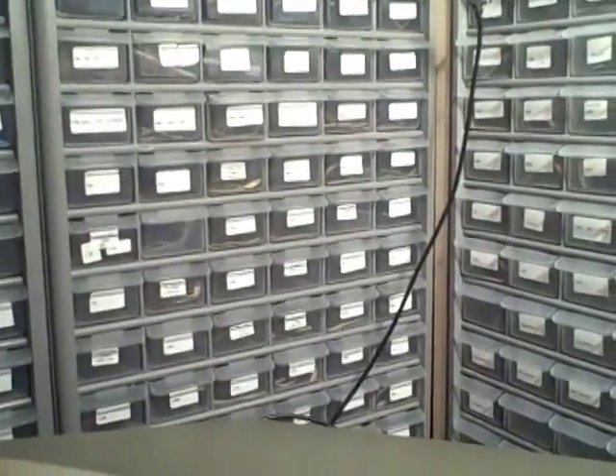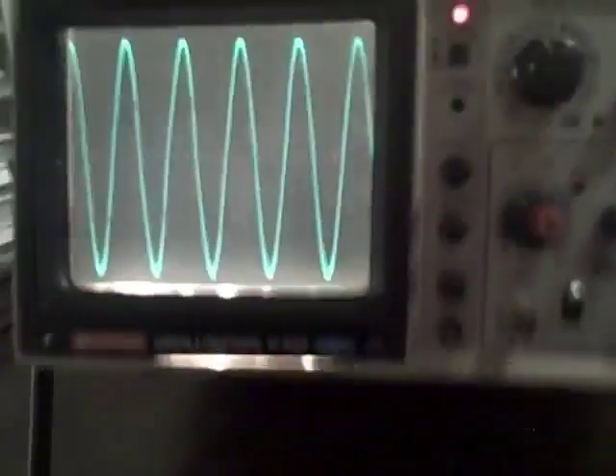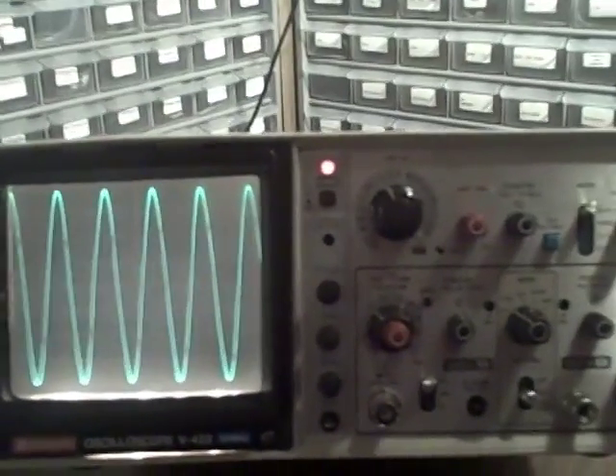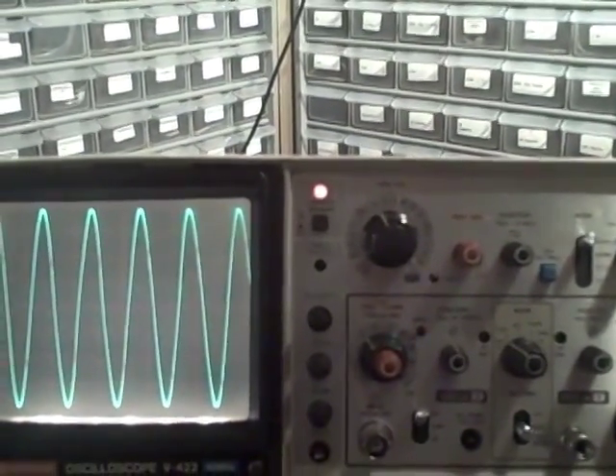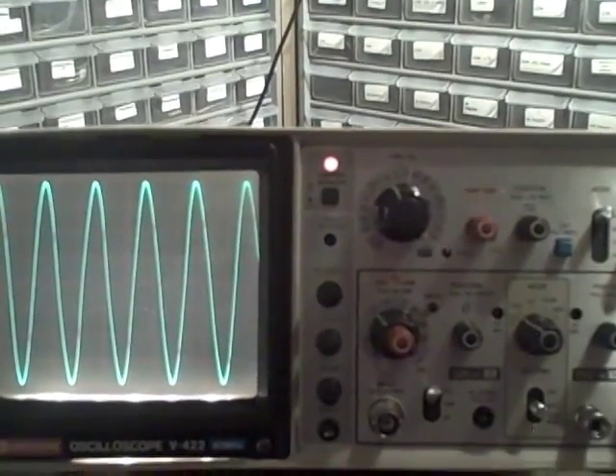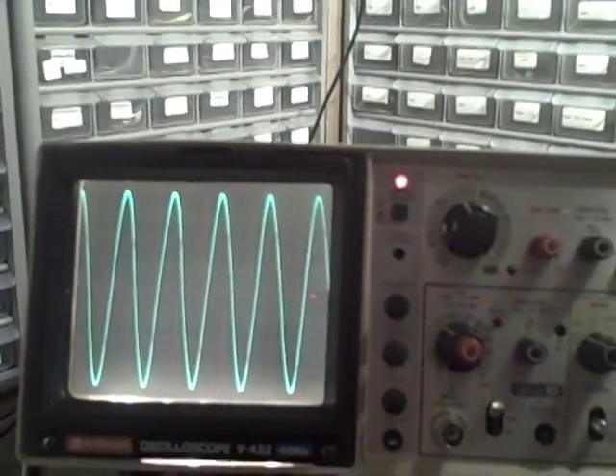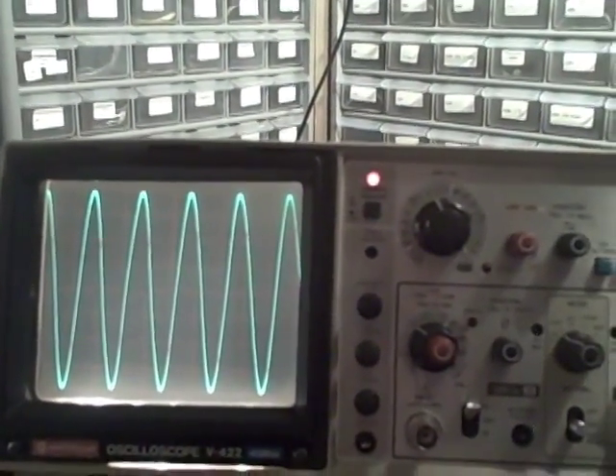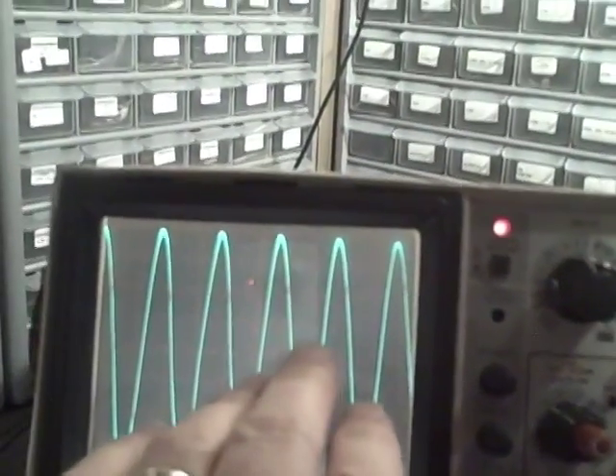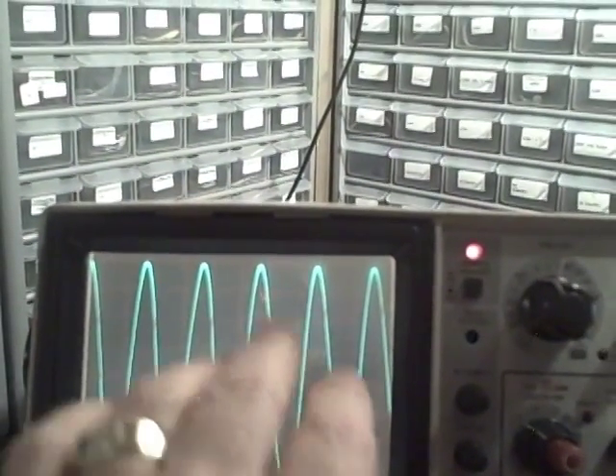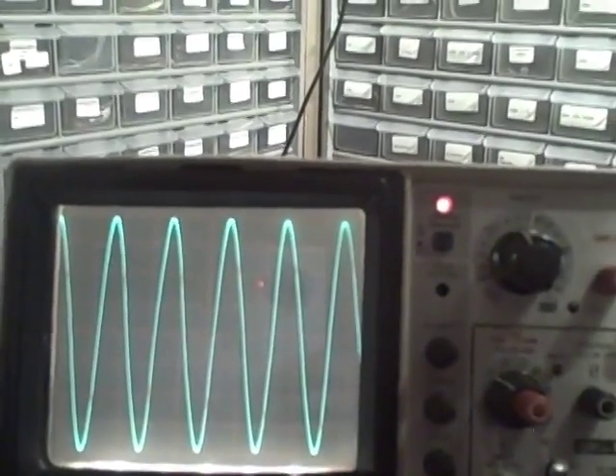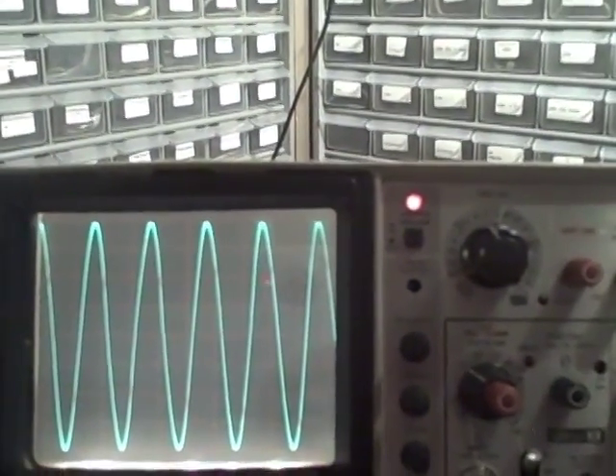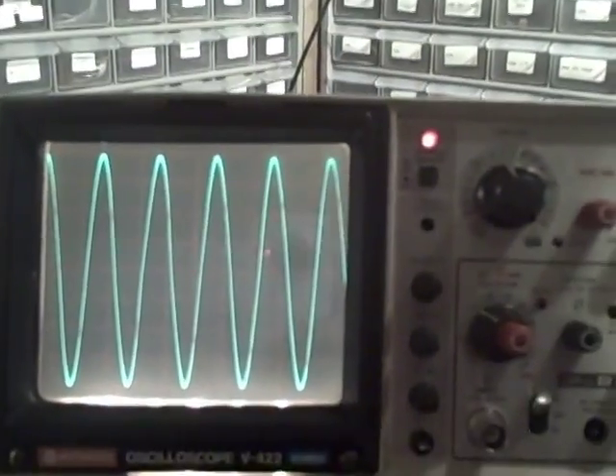I'm going to adjust myself for 100 millivolts coming in. Alright, we have actually 400 millivolts coming in from the generator. We're dividing by 10, that gives us 40 millivolts. We are on the 10 millivolt per division scale, and we see ourselves going up a full 4 divisions, so it's 40 millivolts. 40 millivolts times 10 is 400 millivolts. We're right back to the generator voltage, so that worked well.